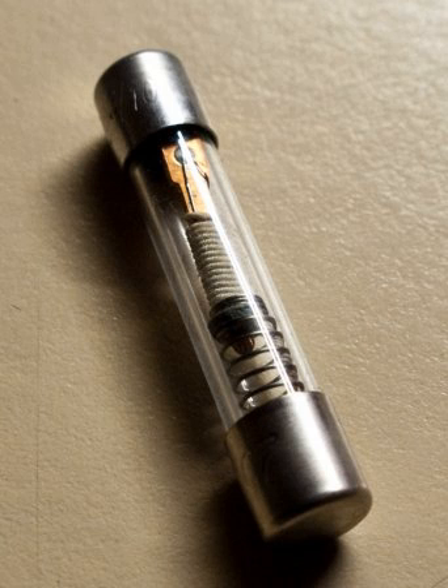So-called HRC fuse switch disconnectors facilitate fuse replacement. They have a hinged cover which accommodates the handle flaps and replaces the fuse handle. HRC fuse switch disconnectors should be operated quickly, as there is a risk of material damage or personal injury due to an arc fault when switching under heavy loads or in the event of a short circuit.